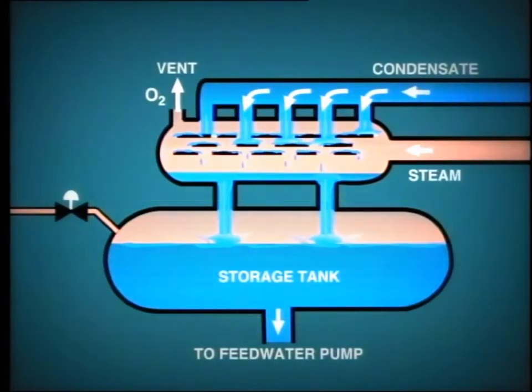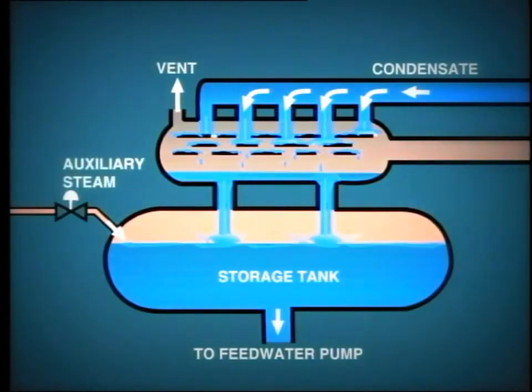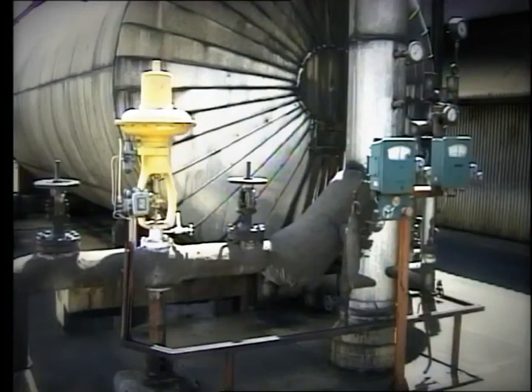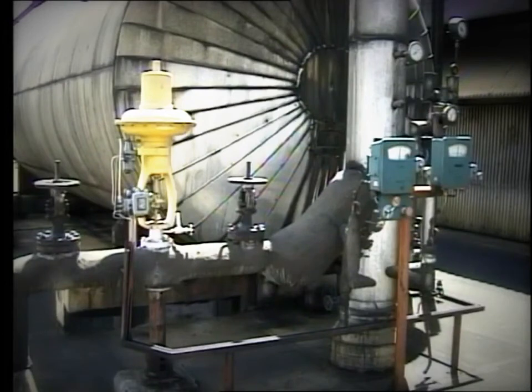During startup of the unit, before extraction steam is available from the turbine, partial deaeration is achieved by supplying live steam to the deaerator. This comes from the auxiliary steam system and is automatically controlled — when the extraction steam pressure falls below an established minimum, the live steam supply opens up.